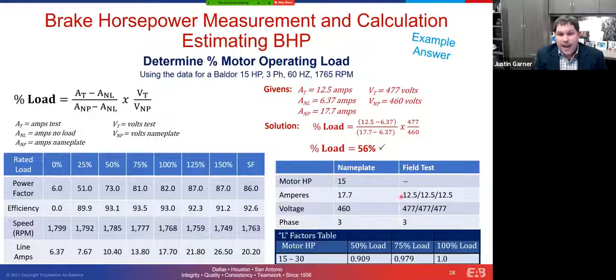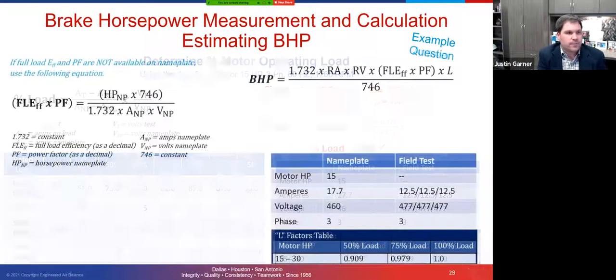That's not what you would get from common thought. I know some folks that would look at this and go 12.5 amps out of 17.7. Well, that's about 60 something percent, right? Well, it's not, it's 56%, because we're looking at the difference between no load and full load. And so it's very important that you run this calculation here. So with that being said, we would take this 56%, look down here at 50% on our L factors table, and we would use 0.909 as our L factor in the next equation.